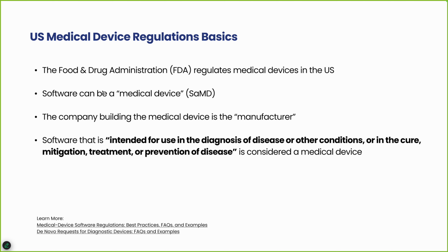So really quick, going through the basics, as I'm sure most everyone here knows, if you're marketing your device in the US, the Food and Drug Administration is the governing body that regulates that. Software can be a medical device. In everyday English, usually you think of a device as being a physical thing, but in regulatory speak, we still call software a medical device. And there's this term software as a medical device, or SaMD, that you'll see frequently used here. And similarly, the company that is building the software is considered the manufacturer.